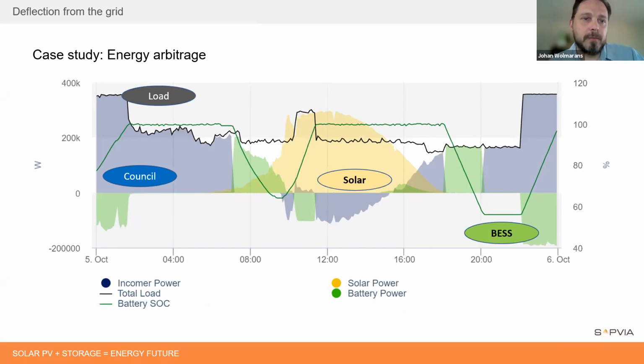In the second case, this customer was interested in energy arbitrage. So it's fairly simple. The battery charges from 10 o'clock at night until about 5 o'clock in the morning, usually as slowly as possible to make sure that you do not affect the max demand too dramatically. And then during summertime from 7 to 10, we discharge the battery. And in this case, you can see the solar picking up quite nicely. So we're only discharging from battery storage early in the morning, and as the PV picks up, that contribution from energy storage becomes less and less.